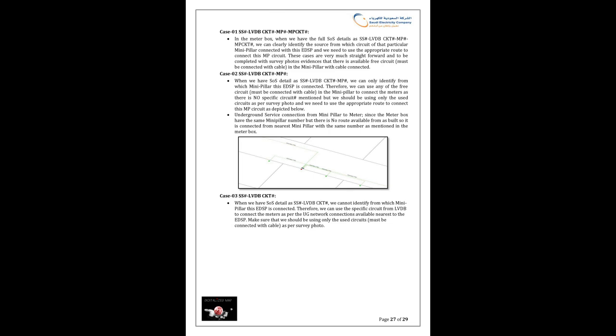Case 2: SS, LVDB, CKT, MP. When we have SOS detail as SS, LVDB, CKT, MP, we can only identify from which mini pillar this EDSP is connected. Therefore, we can use any of the free circuits, which must be connected with cable in the mini pillar, to connect the meters, as there is no specific circuit mentioned. But we should be using only the used circuits as per the survey photo, and we need to use the appropriate route to connect this MP circuit, as depicted below.